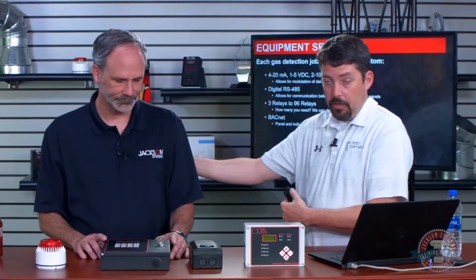Then each panel has 3 relays in it. Those relays, as an example, if I've got 3 louvers and 3 fans, I'm going to bring on all of those at the same time. So I just need 1 relay out of that panel. I got 2 more relays I can do other things with. If I'm going to stage that, or I'm going to zone that where, okay, if the sensors in this area go off and I want the fan and the louvers just in that area to open or start, then we might use all 3, right?